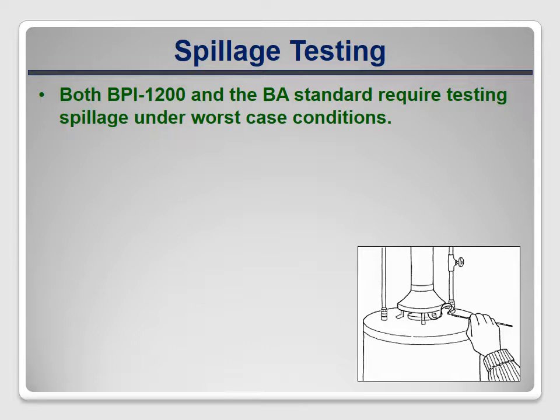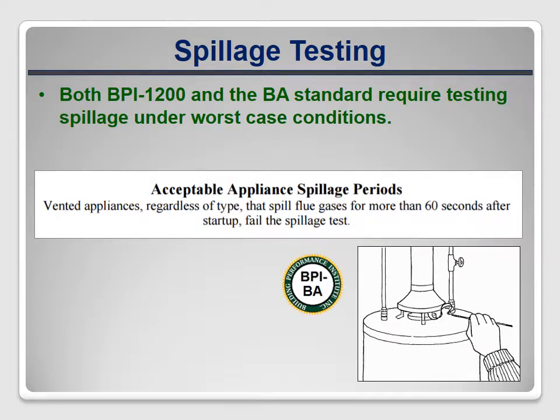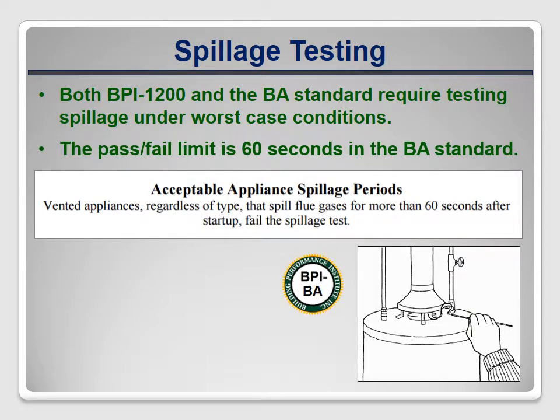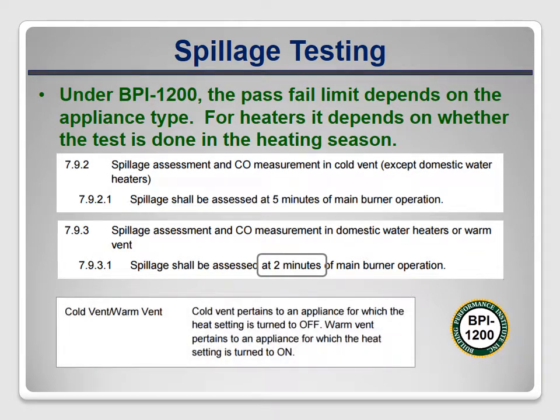Both BPI 1200 and the BA Standard require spillage testing of all vented appliances under worst-case conditions. The BA Standard sets a time limit of 60 seconds for all appliances — if spillage continues beyond that, the appliance fails. BPI 1200 increases the time limit: for water heaters it's two minutes. For heaters with a cold vent (not operating because it's not the heating season), the limit is five minutes. For heaters with a warm vent (currently operating), the limit is two minutes, same as water heaters.